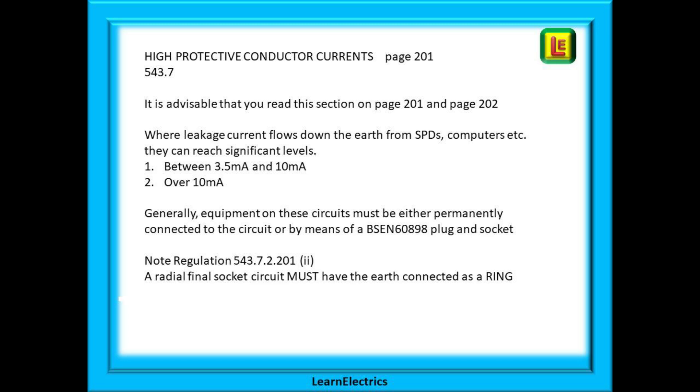Generally equipment on these circuits must be either permanently connected to the circuit or by means of a BS EN 60898 plug and socket. Note especially regulation 543.7.2.201 part 2, a radial final socket circuit must have the earth connected as a ring.